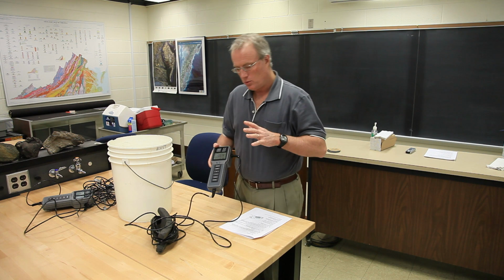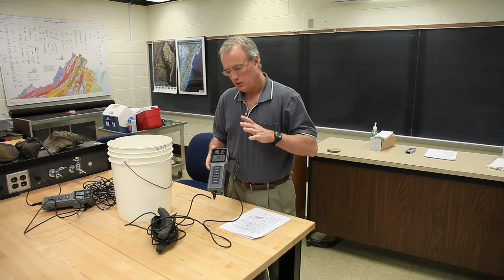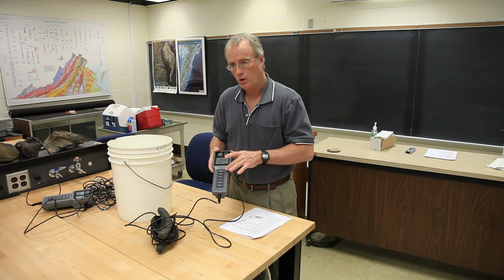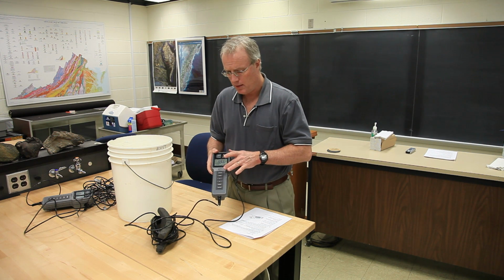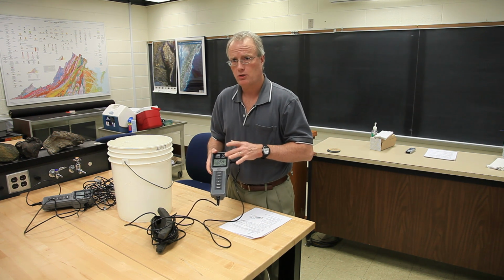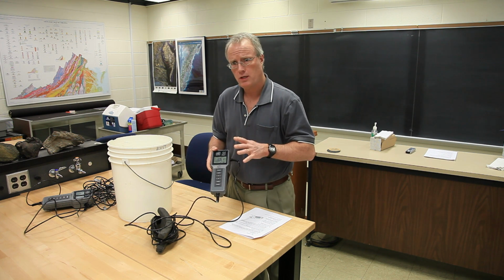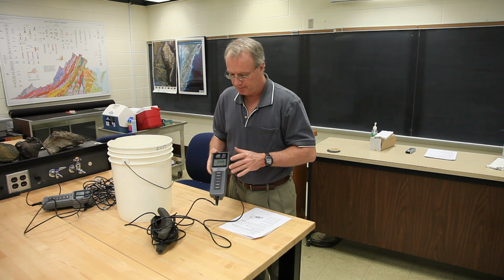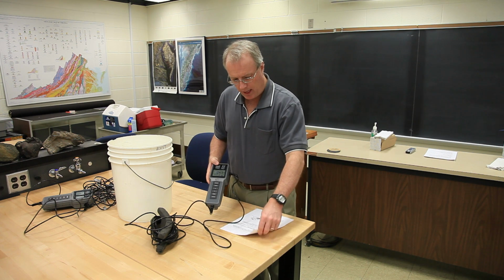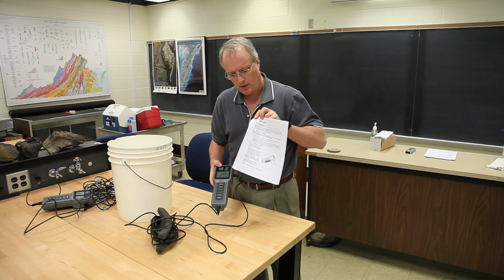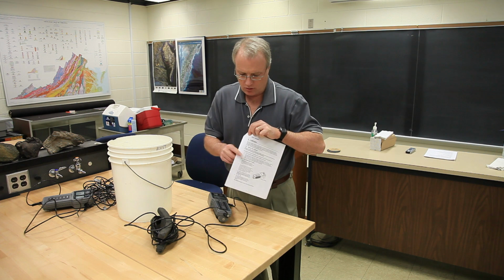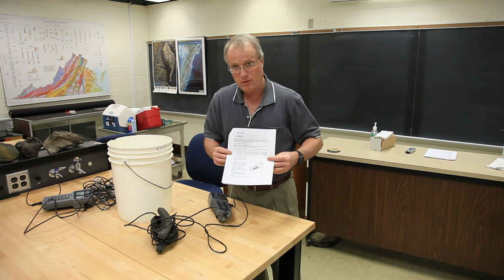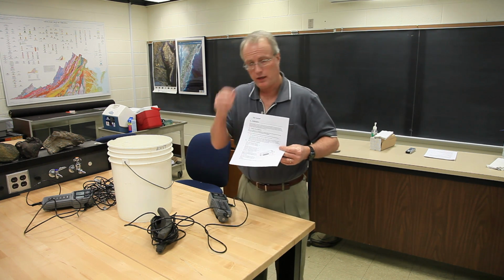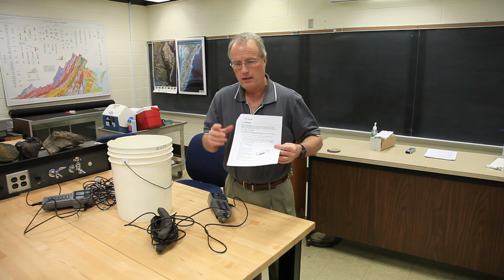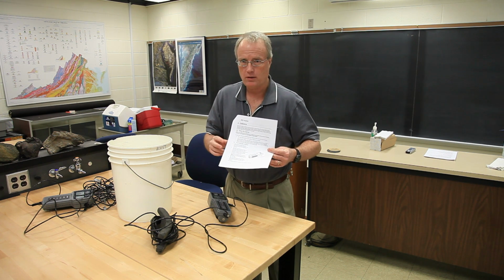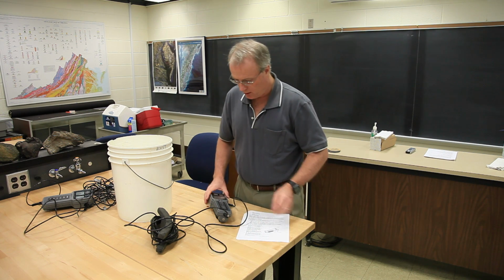So as with all the meters, we're going to go through a two-step process. We're going to first confirm that the meter is working correctly with a quality control step, and then we're going to use it to measure dissolved oxygen in an unknown sample, such as the river that we're at. So how do you do the calibration? Well, the details are on the instruction sheet that you'll be given for the meter, and you have to read these very carefully and do exactly what they say. I'm not going to go through every single one of those steps, but let me point out some important things.